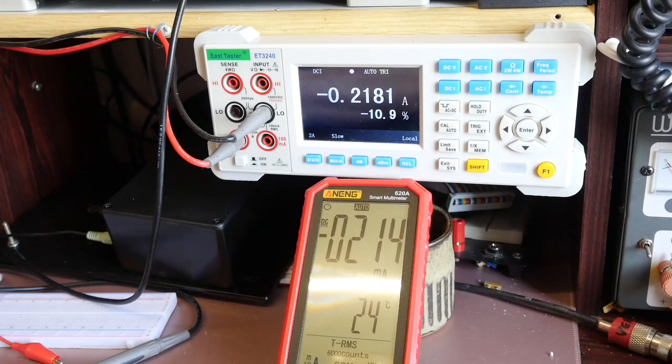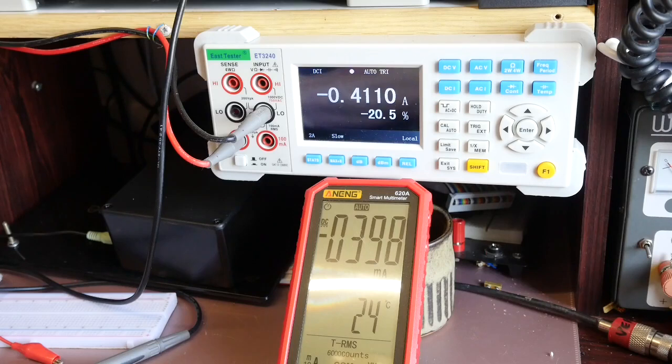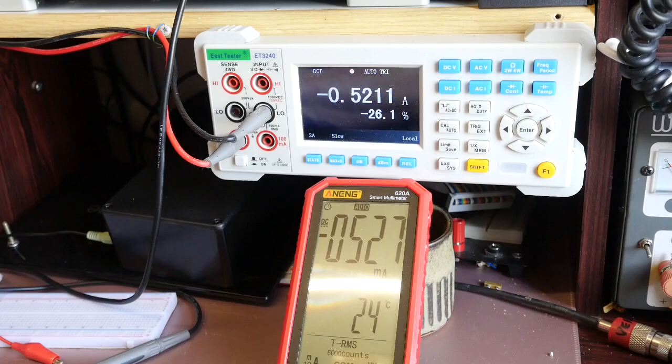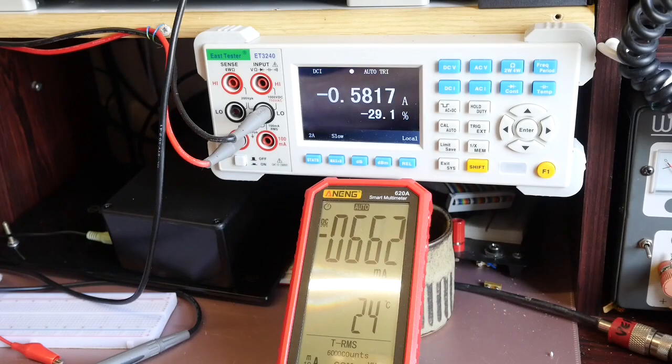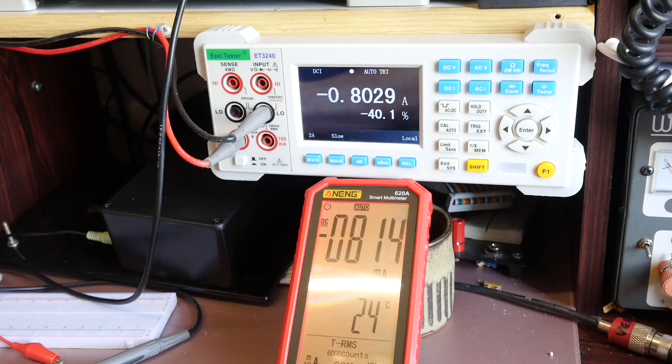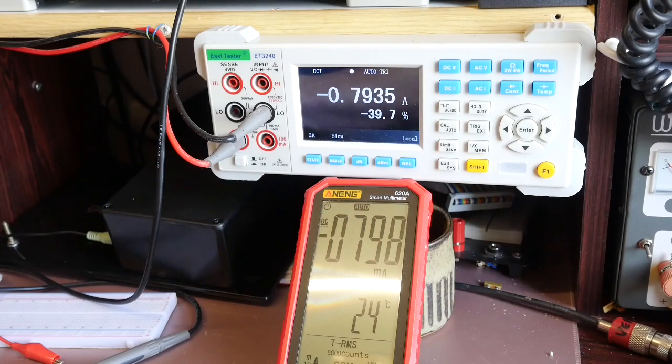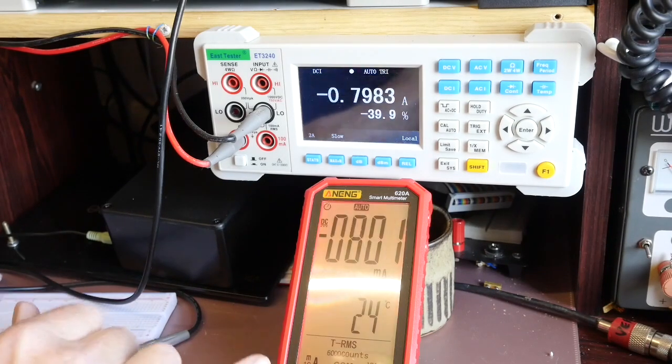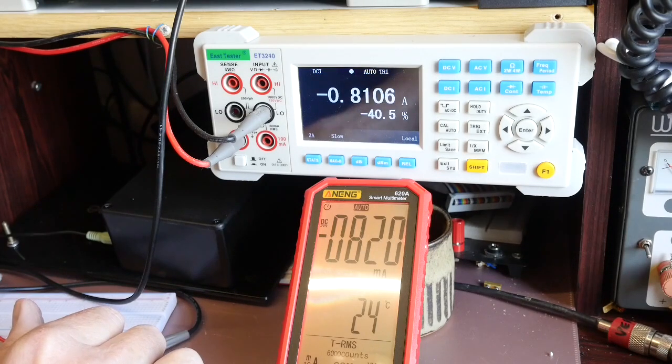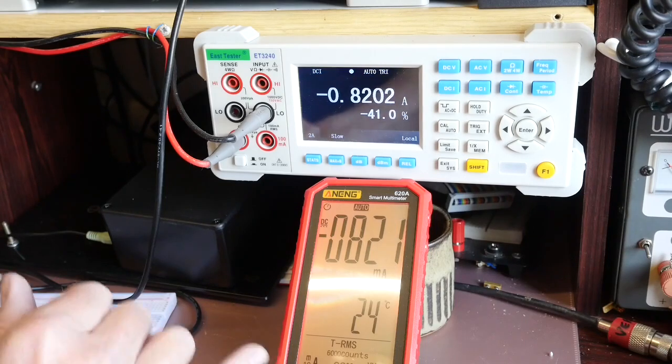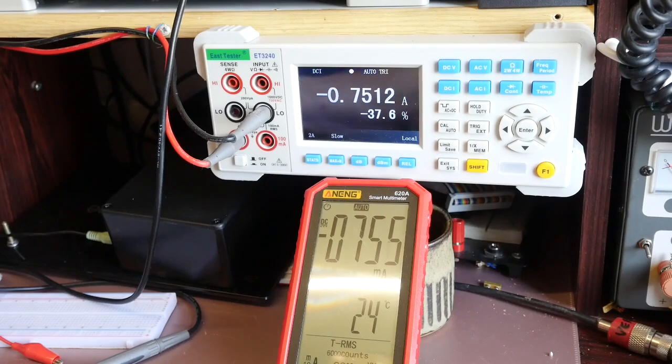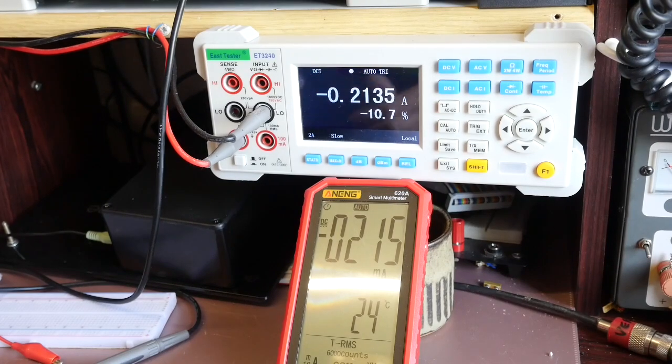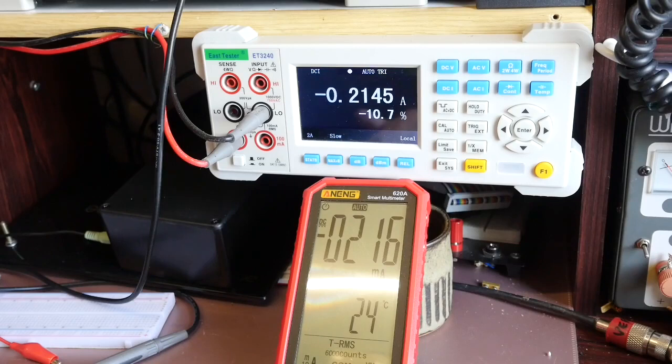So as I decrease the resistance, increase the current, go up to about 500 milliamps something like that and again it's agreeing to within two or three milliamps so seems pretty reasonable. Let's go up there and yeah certainly agreeing at about 0.79 amps. It does actually say maximum 10 amp for 10 seconds on the current measurement here so I'm not going to push it too far.